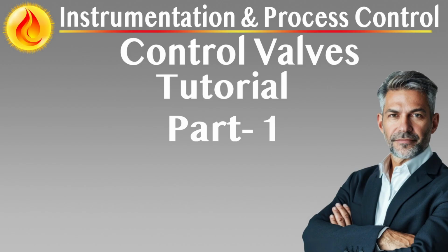Linear valves must be mounted with vertically oriented actuators. Installations shall ensure full clearance around the actuator and body to enable complete valve disassembly without pipe removal. Adequate space for hoisting equipment must be considered during valve location planning.